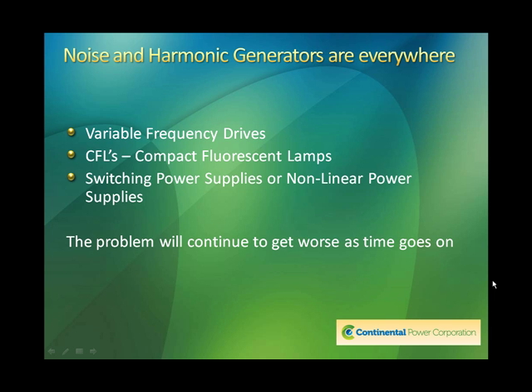We see those noise and harmonics generators almost everywhere. I just showed you the variable frequency drive result, but things like CFLs, or compact fluorescent lamps, are devices that the U.S. government is encouraging, maybe more than encouraging, pretty much demanding that consumers use in place of incandescent lamps, and I understand why. They use much less electricity, but they generate huge amounts of noise because of the switching power supplies, the power supply that drives the actual fluorescent portion of the lamp. Switching power supplies, also called non-linear power supplies, are small, very inexpensive, and very cost effective because they are inexpensive to build and inexpensive to use.